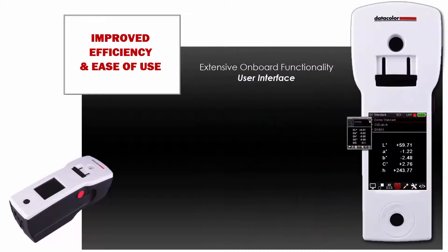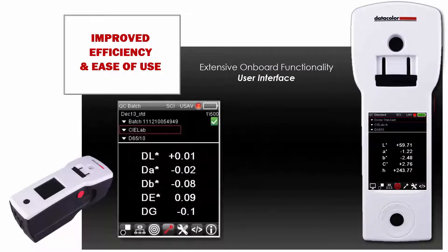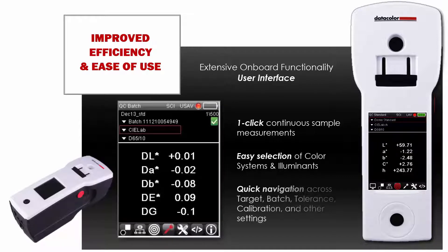Extensive onboard functionality of the instrument's user interface is both efficient and intuitive. A large color screen provides color-coded pass-fail judgment for eliminating QC errors in rapid decisions. The intuitive user interface enables one-click continuous sample measurements, easy selection of color systems and illuminants, and quick navigation across target, batch, tolerance, calibration, and other settings.